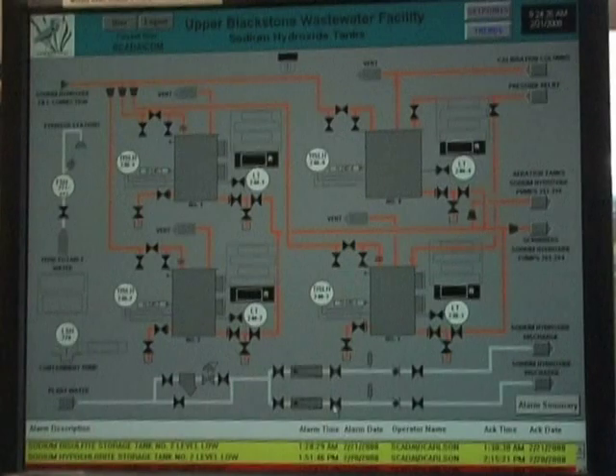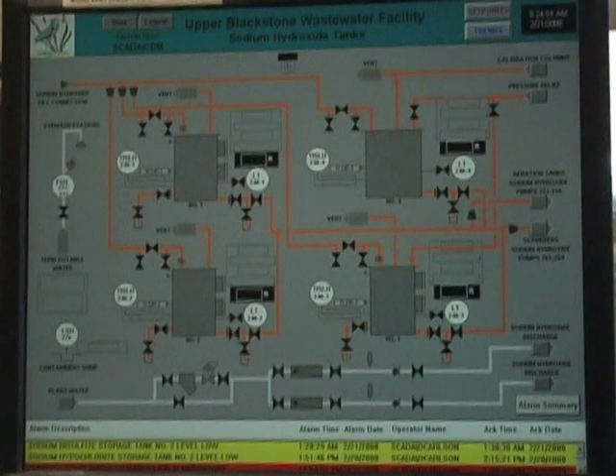Now on this screen you'll be able to get your level alarms. You'll see your actual levels in the tanks. You'll see temperature switch alarms, whether it's high or low, just so we can monitor the temperatures in the tanks. And from here you also have set points for each of your tanks, for a low, a high, high, and a deadband for each tank. And these are the points that will alarm on the screen right here where currently nothing is showing.